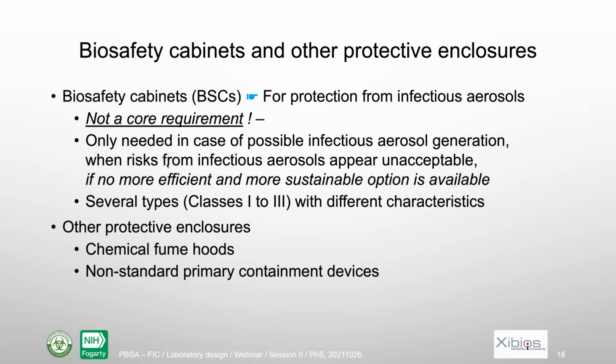It's only needed if there is a risk of aerosol that could be infectious and that risk appears not acceptable in that lab. And also if there is no more efficient and more sustainable option, because in some cases, if it's very limited work where there is some risk of infection through the airborne route, for that specific operation, it's sometimes much easier to wear a mask, for instance. So you see, you don't necessarily need to have such equipment.